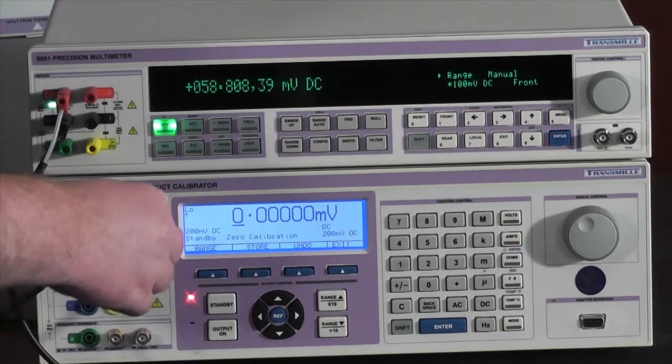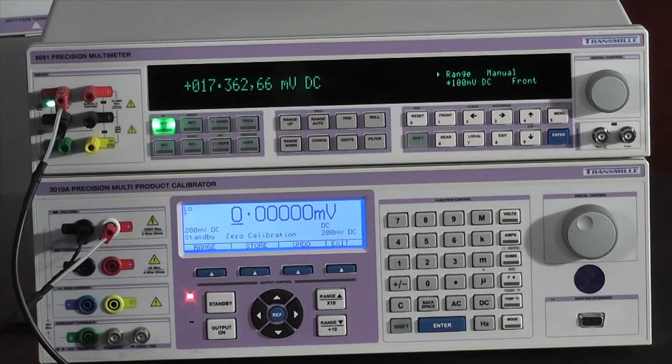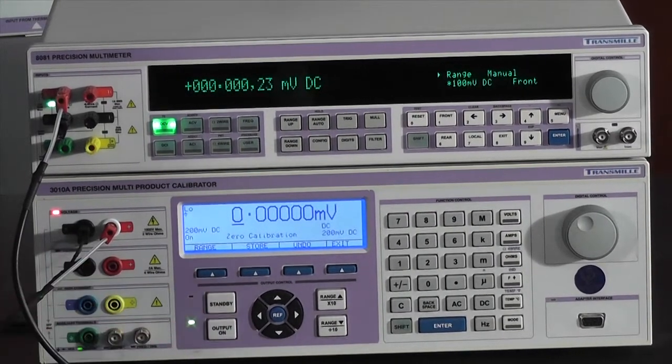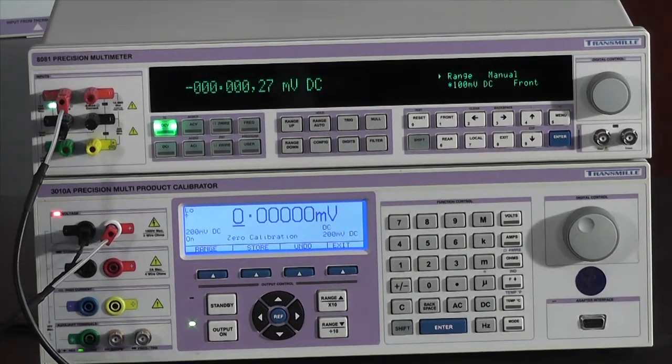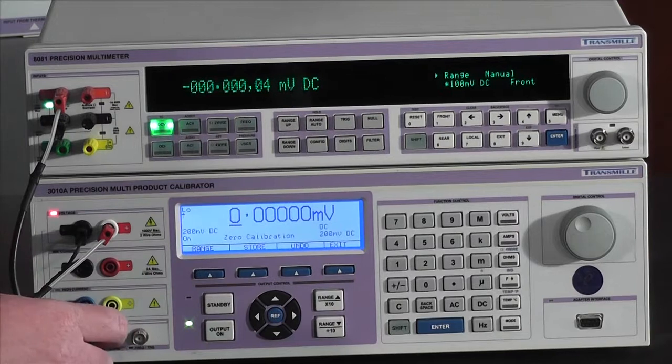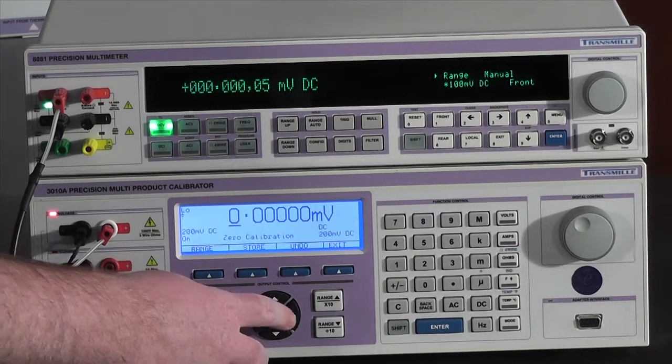Simply connect to the output of the calibrator and press output on. As we see, we have a small offset here that we can trim out.